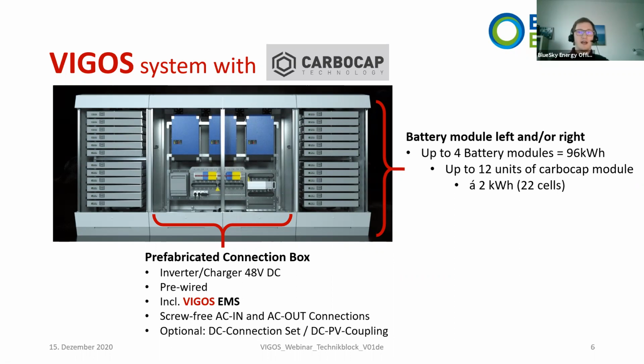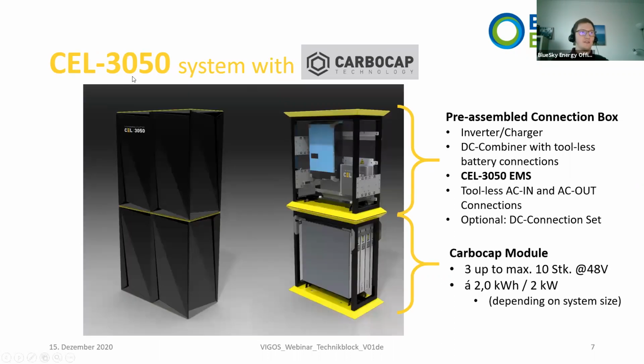So the other product which we made out of this technology is the CEL-3050. So this is a smaller system, but also has the same, let's say, main settings available. So we have a pre-assembled connection box where an inverter and charger is placed inside. We have a so-called DC combiner with toolless battery connections where you can connect up to 10 pieces of this module. So with each 2 kilowatt hours. So in here in the picture, you see 5 modules standing in this rack. One module, same with Vigos, has 2 kilowatt hours in capacity and up to 2 kilowatts on power, depending on the system size.